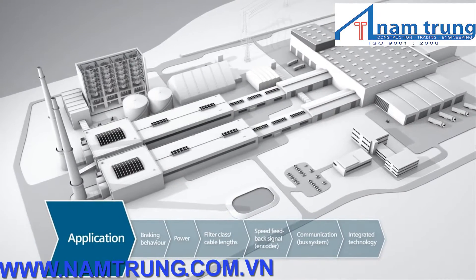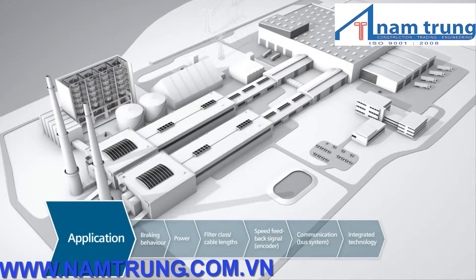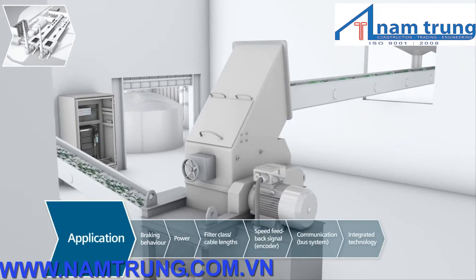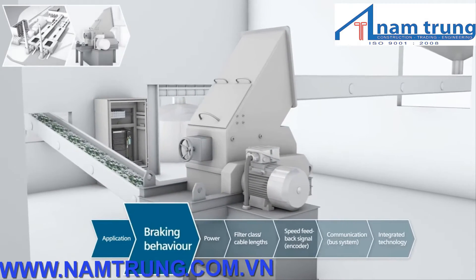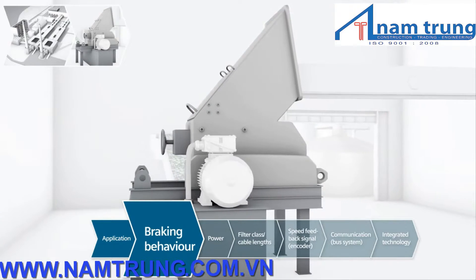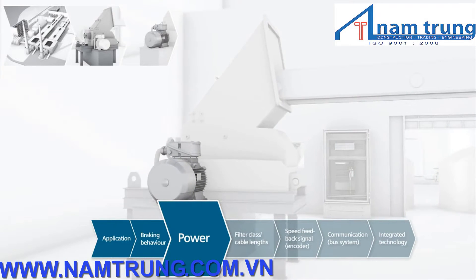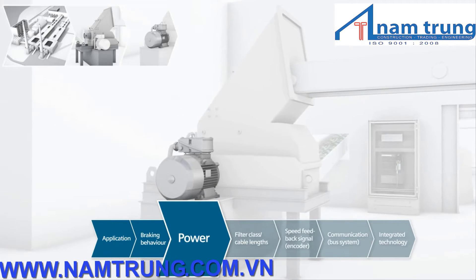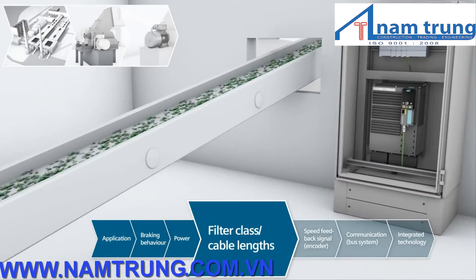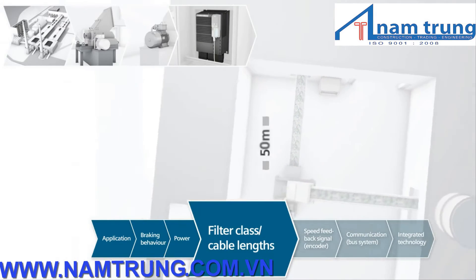What type of application is involved here? Sinamics G120 can be used in several processes in this application — for example, the crusher that crushes the recycled glass. What are the technical requirements of the crusher regarding its braking behavior? As a result of the internal friction in the crusher, the machine immediately comes to a standstill — neither a braking resistor nor energy recovery is required. The power rating of the crusher motor is 15 kilowatts. A class A filter must be used in this industrial environment, and an output reactor is not required as the cable length is only 50 meters.